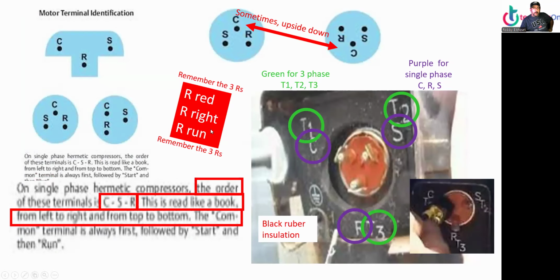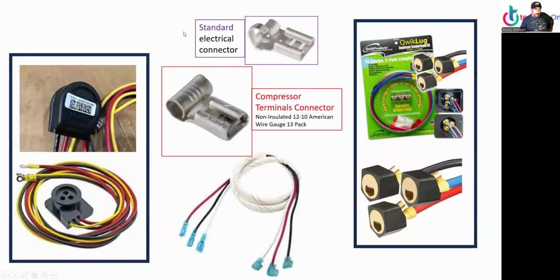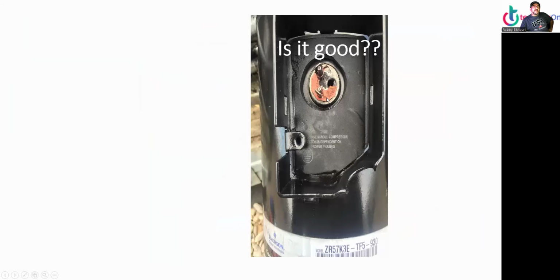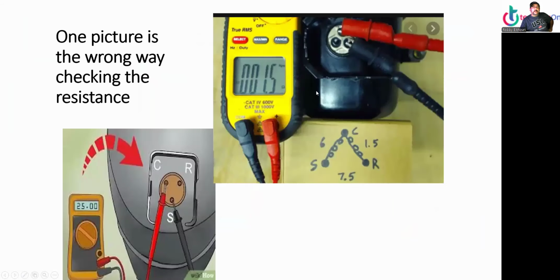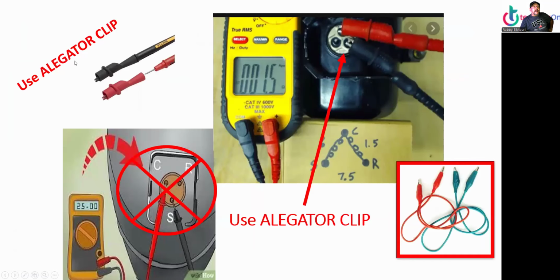That's not true. Okay. So we have a standard electrical connection, a compressor connection. They look the same, but a little bit different. This is a good connection. Make sure there are no issues. Is this good, boss? Broken compressor? All right. So one picture is the wrong way to check the resistance. Which one's the right way? Which one's the wrong way? Use alligator clips. This thing is so tiny, your hand moves. You gotta use alligator clips to check for resistance.